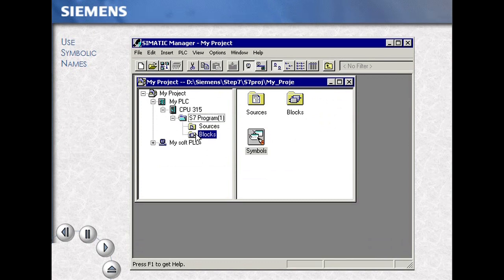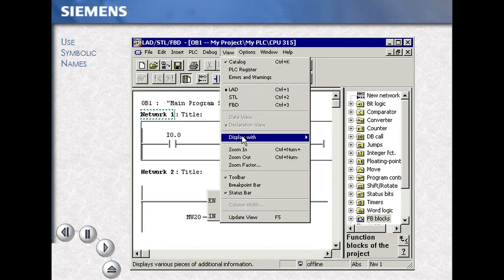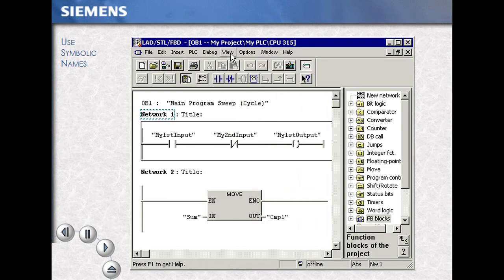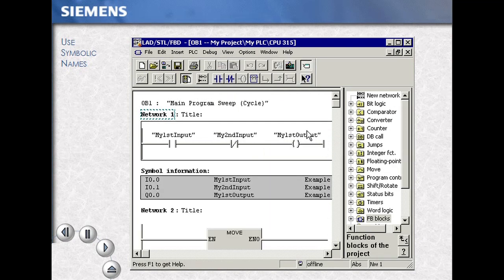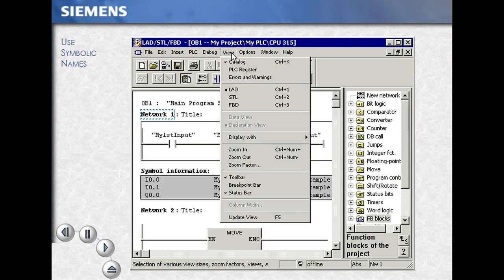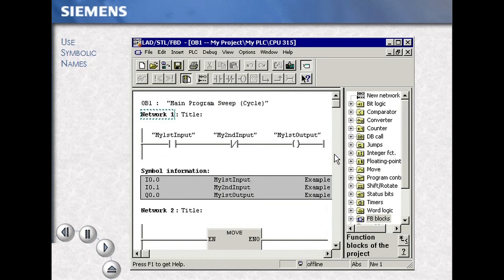Continuing, we open the blocks folder, opening a code block with a double-click. We now turn on all the symbol choices under View, Display with, Symbol Representation, Symbol Information, and Symbol Selection. You can turn on all, or one, or two of these. You see the symbol information and the symbol name on the screen at the same time.